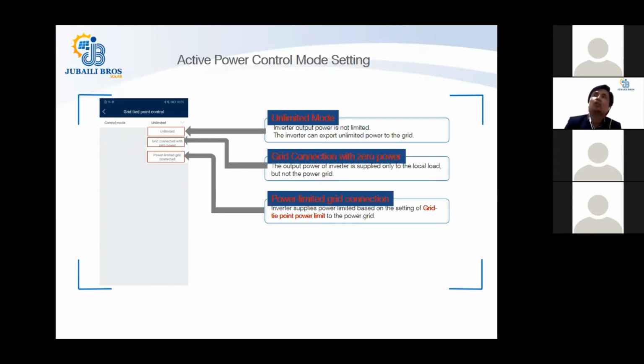In the active power control, you also have an option of not looking at the grid tie point and instead directly doing the control, such as limiting your 50 kilowatt inverter to 25 kilowatt, so that it doesn't give more than 25 kilowatt of power. Such control doesn't require a power meter installed at your point of connection constantly monitoring and feeding data to your inverter, because you have limited your inverter, which reads the generation of your PV side and then controls. If it is below the 25 kilowatt, it doesn't require curtailment of your PV system. If it does, the inverter will do it without the need of a power meter. So we will speak about both scenarios.